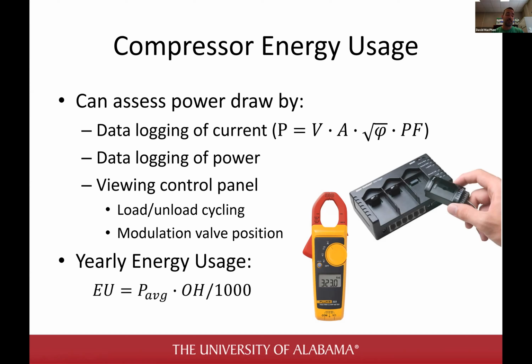So you go to the compressor, put the data logger on one of the three leads to measure current, and you can get a surrogate for power draw using this equation. You'll need the voltage (V) times the amperage (A) times the square root of phi, the number of phases of power. That's 3 for almost everybody with a facility using 480 volt three-phase power. If you have 120 volt single phase power like in homes, it's just the square root of 1.